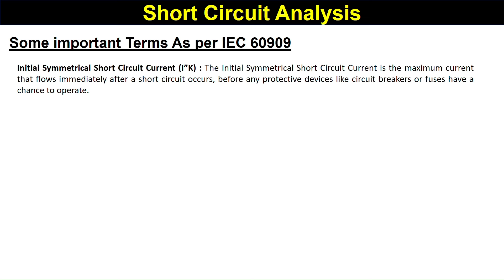There are some important terms as per IEC 60909, the standard used for short circuit analysis. The first term is the Initial Symmetrical Short-Circuit Current. This is the maximum current that flows after a short circuit occurs, before any protective device like a circuit breaker or fuse has a chance to open. The starting value of the short-circuit current before any protective device operates is called the Initial Symmetrical Short-Circuit Current.